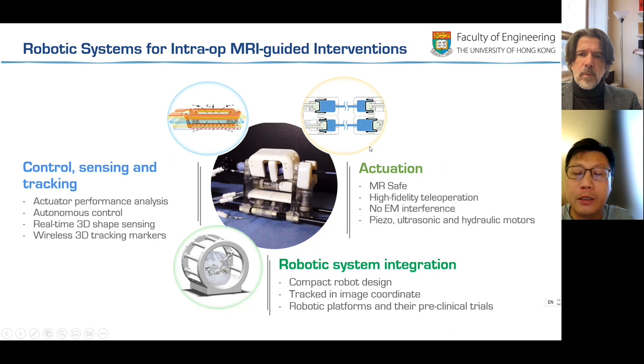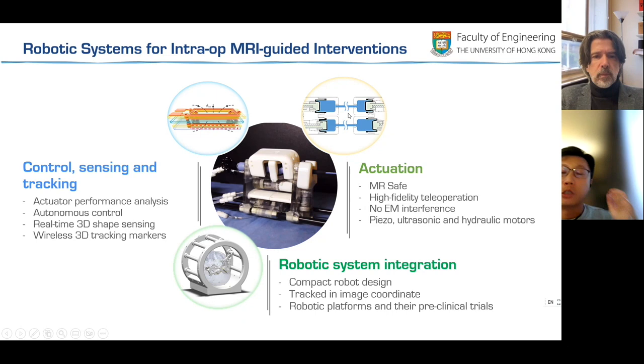That means the conventional EM motor cannot be put inside the MRI environment. So the EM motor has to be put outside the MRI environment, in the so-called control room, to transmit the motion into the MRI room. We usually use hydraulic actuation, hydraulic transmission, because hydraulic transmission with, for example, water or other sodium solutions, is very clean with no EM interference. So we ensure no EM interference is induced into the MRI images.